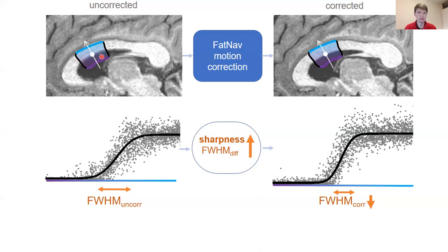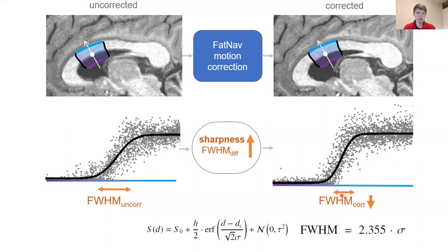We model the intensity at the transition boundary over this region of interest using error functions — sigmoid-shaped functions that show this boundary. After correction, we expect this boundary to be sharper, so that if we measure the full width at half maximum of this function it would reduce, providing a metric for increased sharpness in our image. By using error function parameterization we maintain this in physical units in millimeters, allowing us to relate it to the resolution of the acquired data.